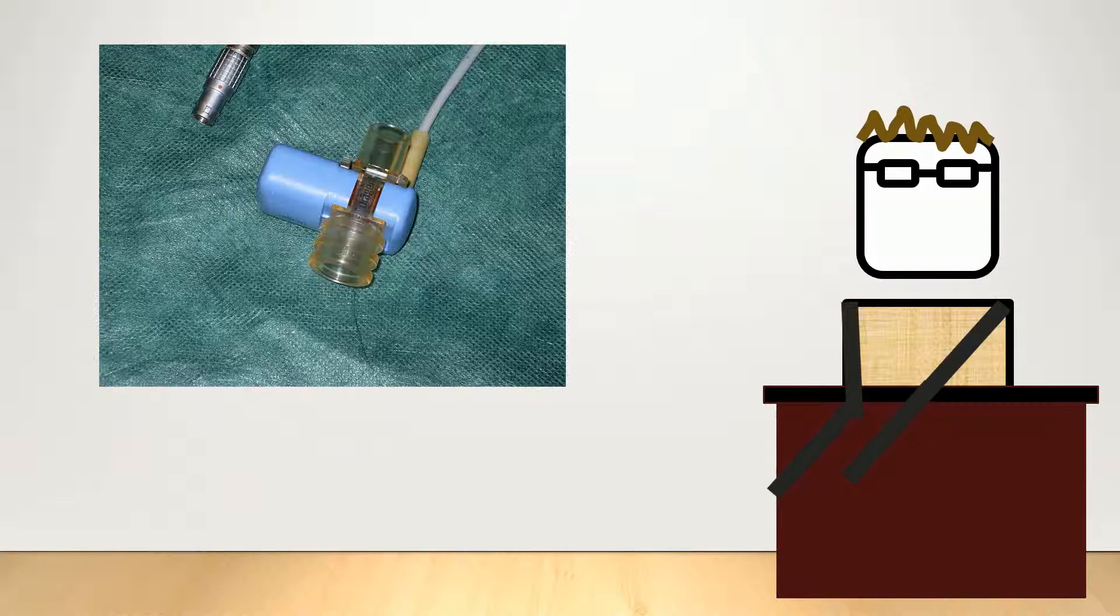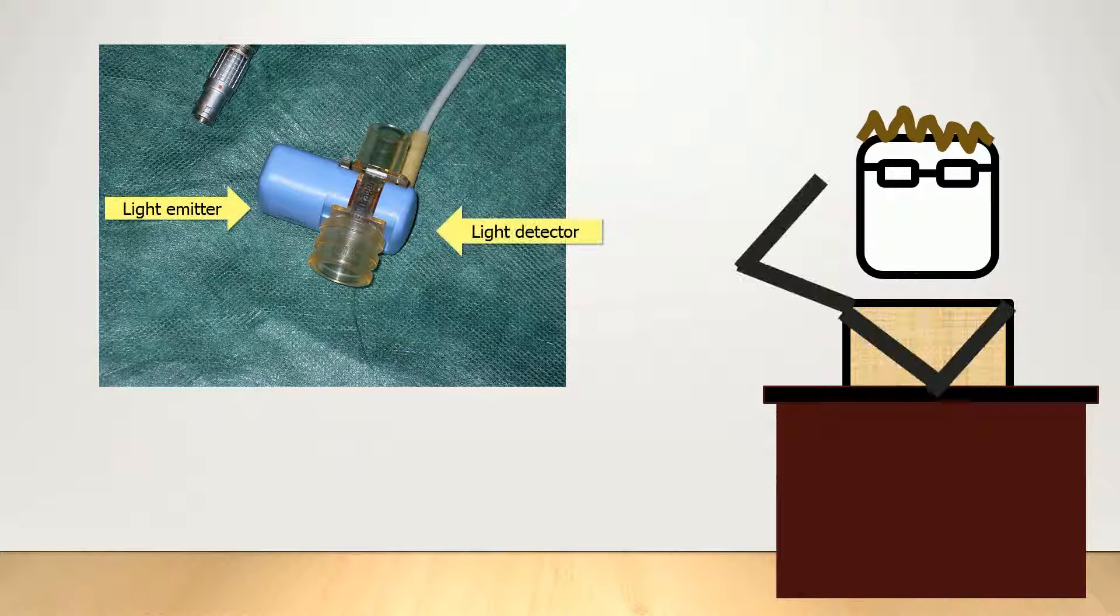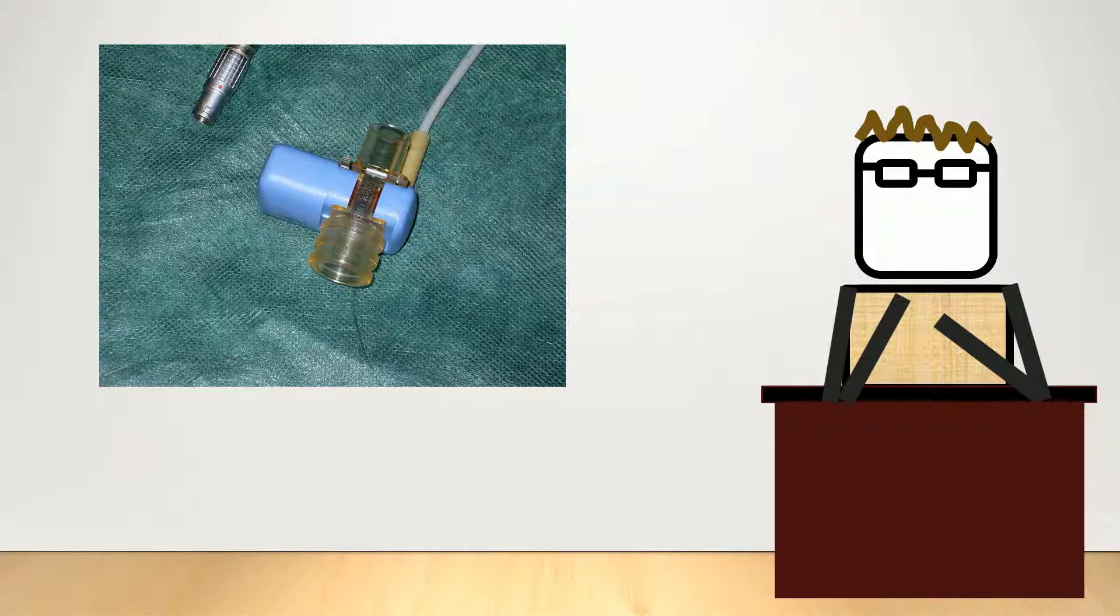Fortunately, we have capnography now. This is a non-invasive way to measure carbon dioxide levels in the exhaled breath. It works on the same principles as the oxygen saturation probe, with a light emitter and a detector on the opposite side of it. The difference, though, is that the light is in the infrared range, so when you look at the capnograph, you can't actually see the light.